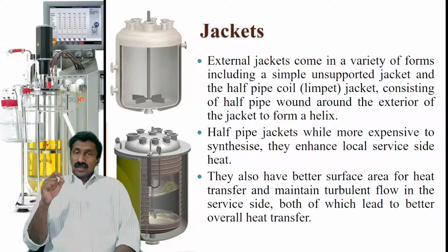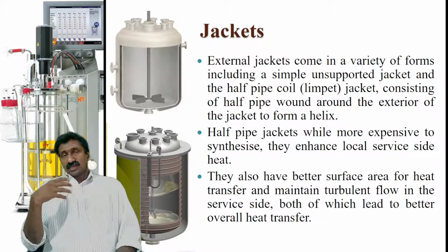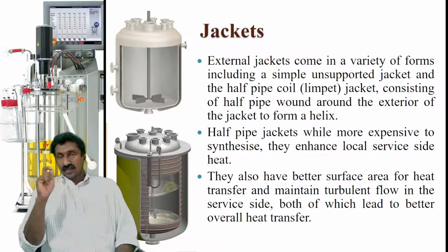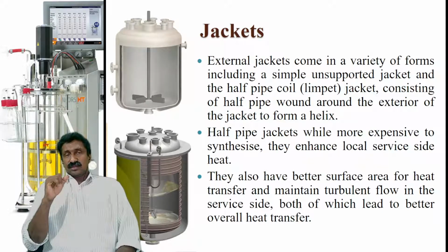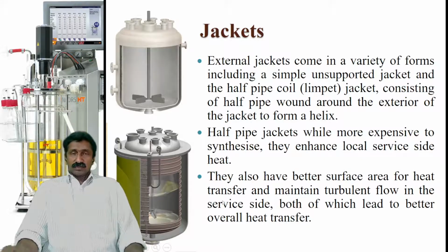The half-pipe jackets, while more expensive to synthesize, enhance the local service side heat. So better heat transfer efficiency can be achieved by half-pipe or limpet jackets. I will show you a picture later. And in the lower picture, this is actually a limpet jacket or a half-pipe jacket, in which additional pipes were wound around the external jacket instead of providing a space filled with fluid all around. It provides a tubing system or a half pipe system, which is wound around the internal vessel. So I can show you another picture in the next slide.